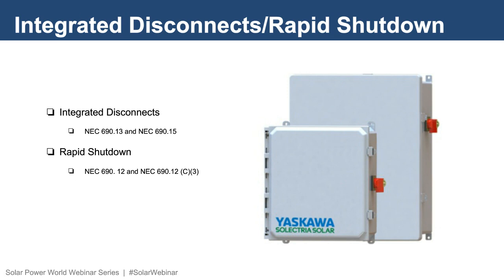The NEC requires that the PV system have a means to be disconnected from all other electrical systems. That's 690.13. Additionally, PV system equipment must have a means to be disconnected from all electrical sources in 690.15. Inverters that have integrated disconnects make it easy to meet these requirements. As for rapid shutdown, it is important that the inverter manufacturer provide or specify a solution to meet NEC 690.12. An important feature that is many times overlooked in inverters is the integrated disconnects. Units that have integrated AC and DC disconnects make system design and installation easier, reduce BOS costs, and simplify maintenance and troubleshooting efforts.